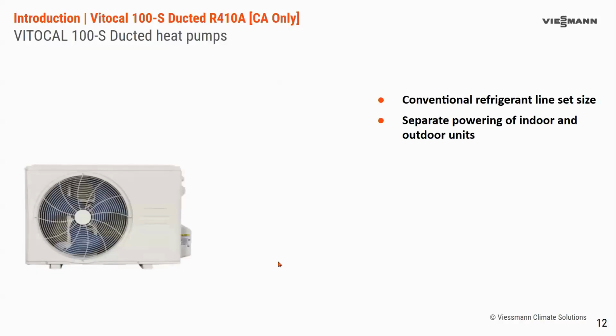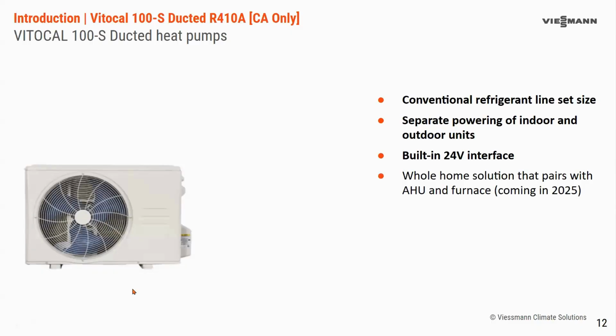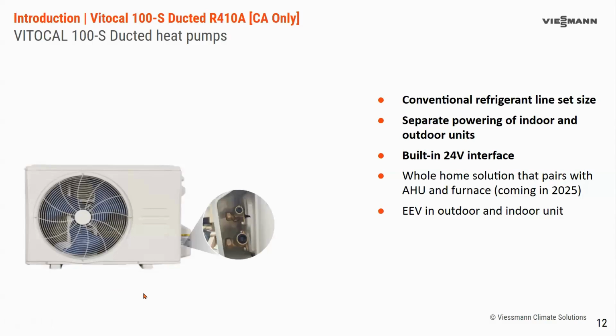Again, conventional refrigerant line sets. The outdoor unit and indoor unit aren't wired the same way as ductless, so mind the installation instructions. This is more like a traditional installation where there's power at the indoor and outdoor unit separately, and there's a built-in 24 volt interface, as well as a solution for pairing with the furnace case coil that we discussed. And there's EEV in heating mode only, so that allows there to be an EEV or a TXV at an indoor unit, whereas the ductless units have EEVs on heating and cooling at the outdoor, and that would interfere with the metering device at an indoor unit, and that requires, in some cases, modification. So that's a reason why you'd want to go with the ducted if you're just strictly ducted.